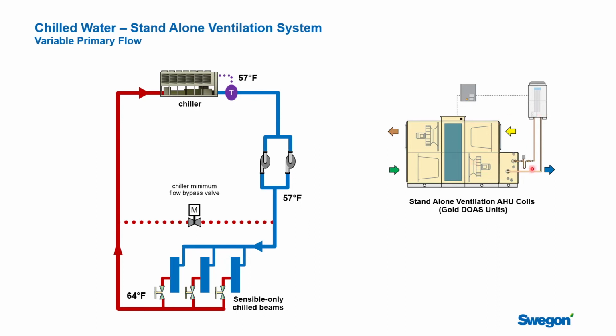In most cases, we design these systems to deliver 55-degree air, and in most parts of North America, with good energy recovery, you can warm up outside air up to 55 degrees just by borrowing the heat through your energy recovery device. You'll find that you'll run almost no hours in heat pump mode if you're supplying 55-degree air. If you have a warmer design, 60, 65, or 70 degrees, you will have some hours on your heat pump, but that's straightforward to do. Of course, if you have natural gas in the unit, that would be straightforward as well.